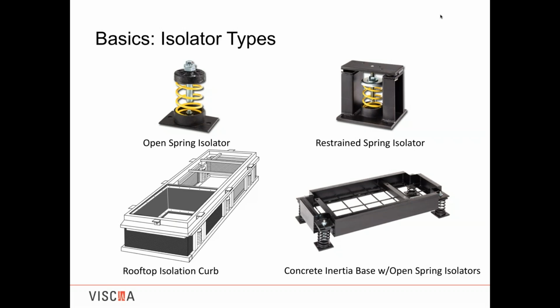That is independent of the static deflection. So when we're talking static deflection, we're not talking full movement. So when you look at that restrained isolator, the space between the upper plate and the lower housing is roughly only 3/8 of an inch. Even if I had a 4-inch deflection isolator in there, that's still enough so that I'll never have contact during operation between the top and the bottom.